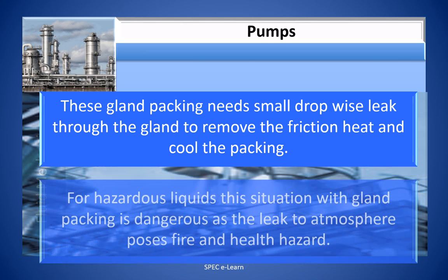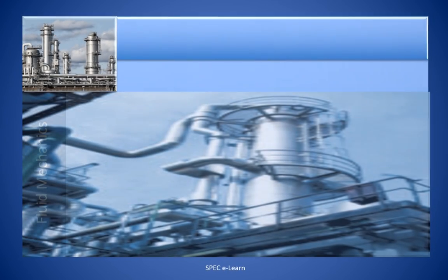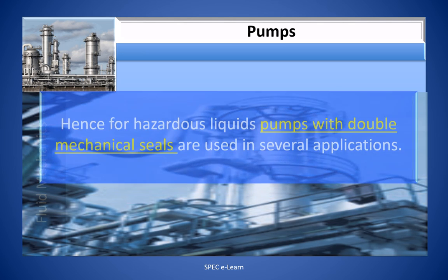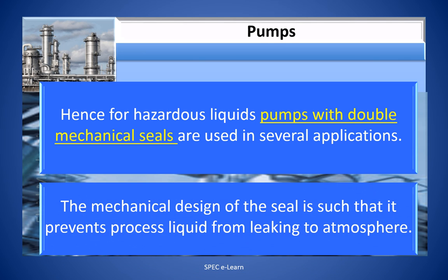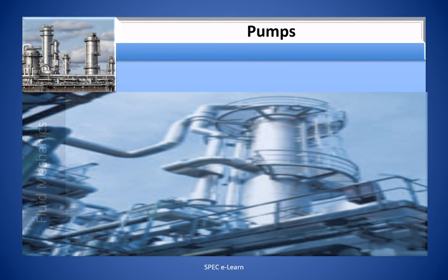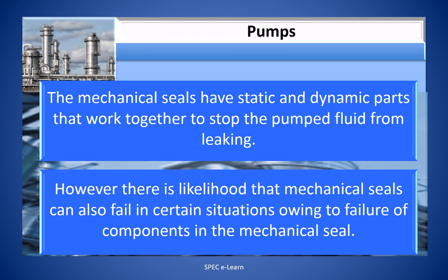For hazardous liquids, this situation with gland packing is dangerous as a leak to atmosphere poses fire and health hazard. Hence, for hazardous liquids, pumps with double mechanical seals are used in several applications. The mechanical design of the seal is such that it prevents processed liquid from leaking to atmosphere. The mechanical seals have static and dynamic parts that work together to stop the pumped fluid from leaking. However, there is likelihood that the mechanical seals can also fail in certain situations owing to the failure of components in the mechanical seal.